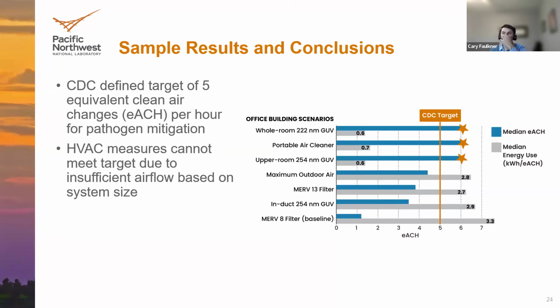I'll talk about some of the sample results from this. This one focused more on the energy aspect as well as calculating these equivalent clean air targets, compared to infection risk modeling. In particular, around the time of the pandemic, the CDC defined an equivalent clean air target of 5 equivalent clean air changes per hour. A lot of times we think of air changes per hour from ventilation from the HVAC system, but the equivalent allows us to count air changes per hour from filtered air, outdoor air, as well as air with pathogens that have been inactivated by the GUV systems.